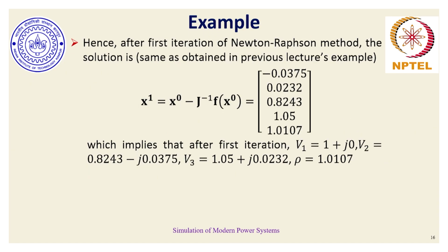So with this Jacobian, if I substitute the corresponding numbers and do the factorization, this is my update vector, where this pertains to F21, this is F31, E21, E31, and this is rho. The first 4 elements are the same that we saw in the Newton-Raphson rectangular version coordinate, which is what gives these voltage vectors.